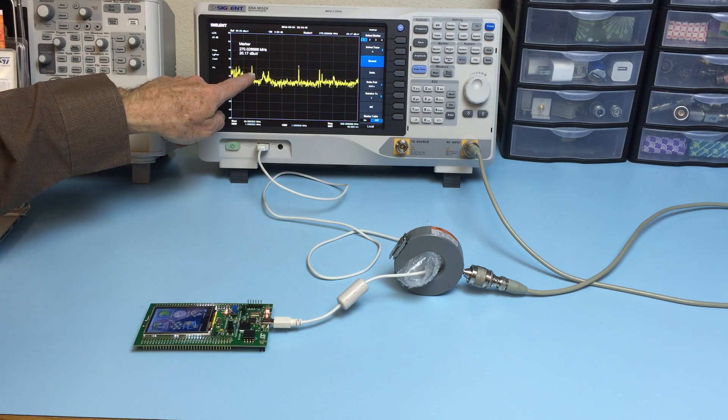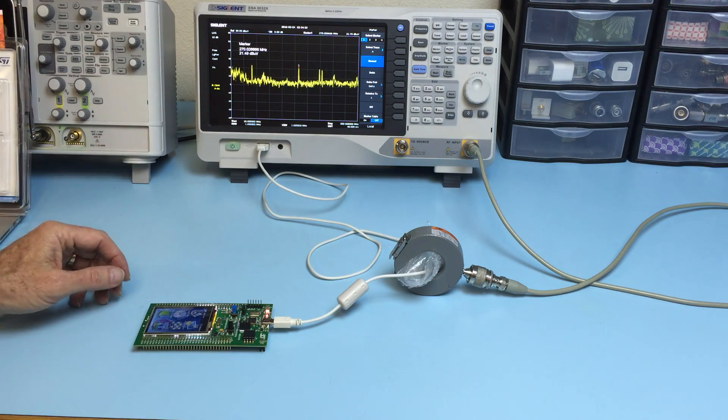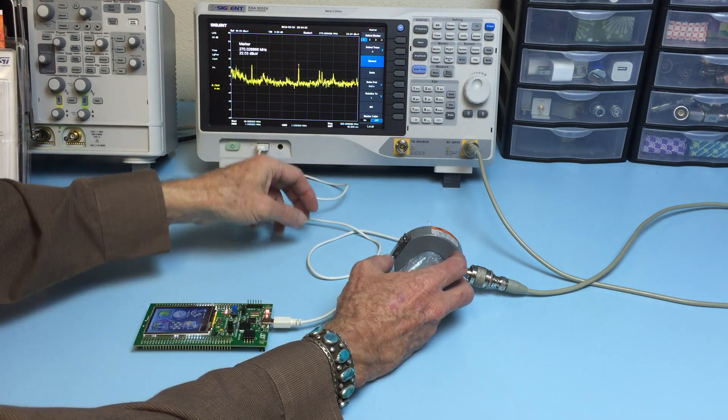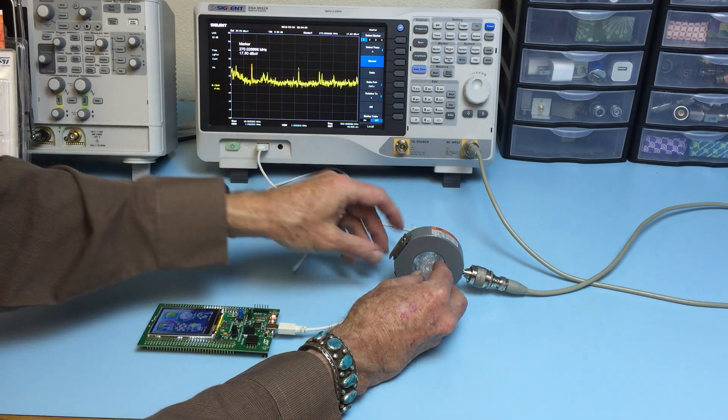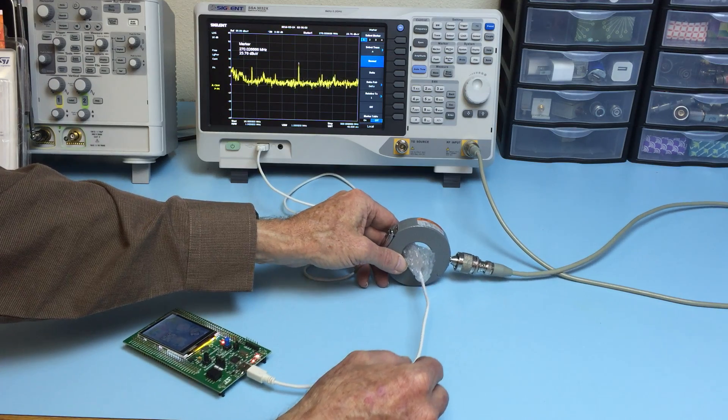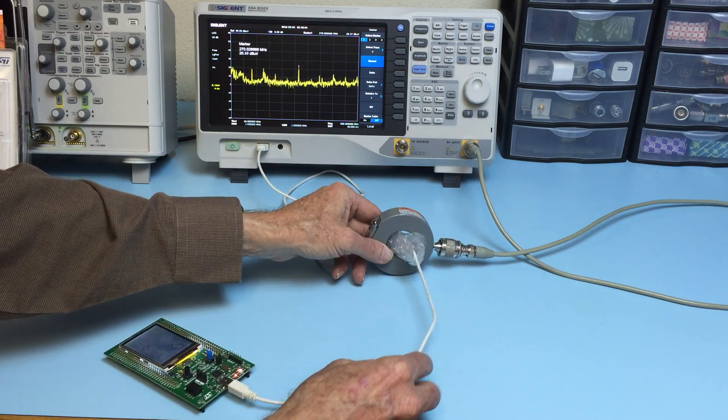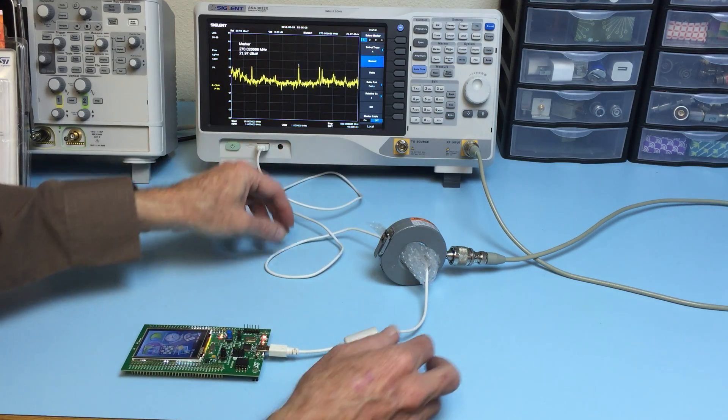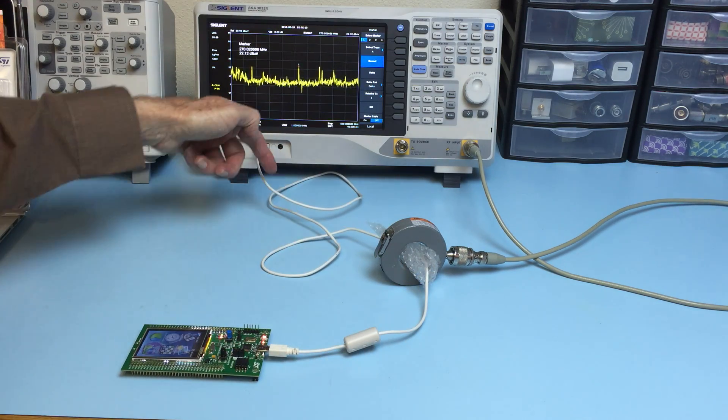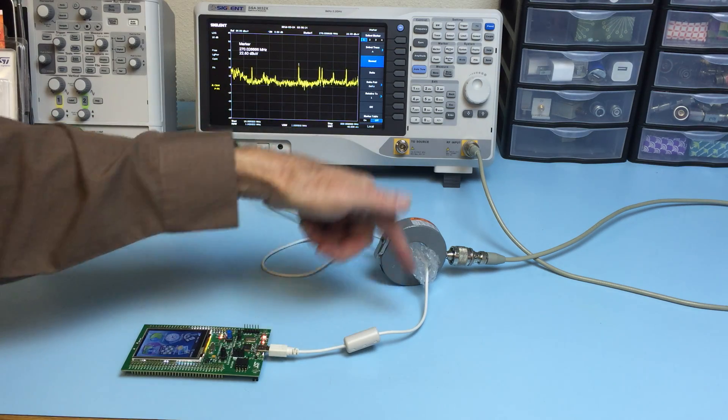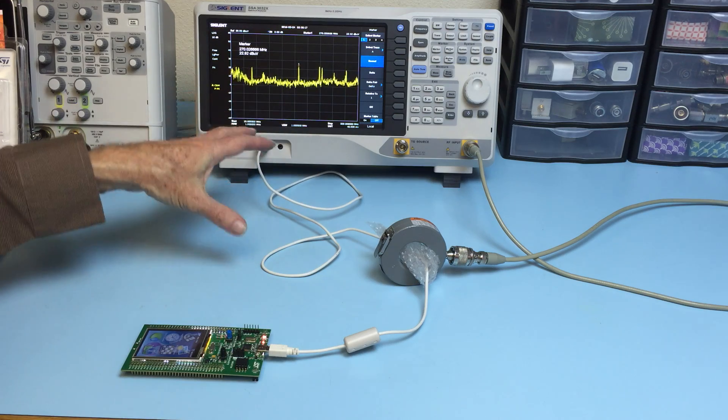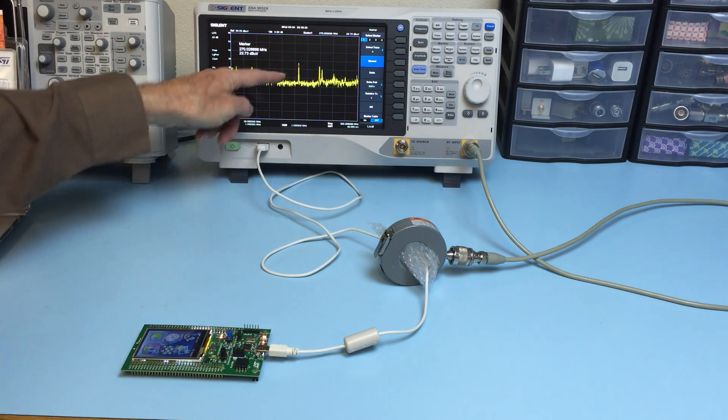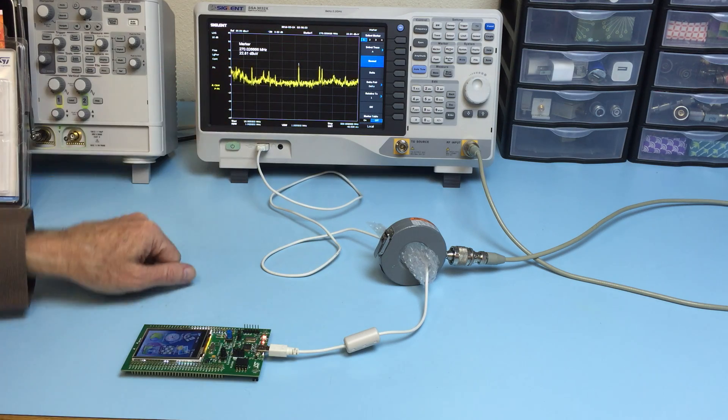These are narrowband emissions, and so what you want to do with the current probe is slide it back and forth on the cable to try and maximize the emissions. The reason you need to do that is because there are so-called standing waves along the cable due to resonances, and so you want to try and peak up the higher harmonics.